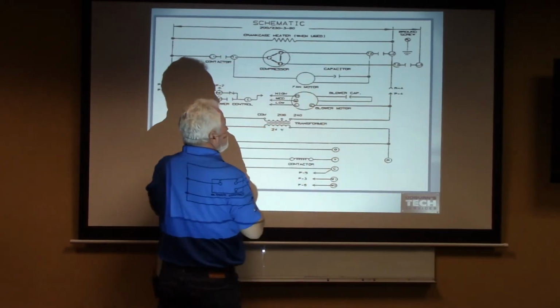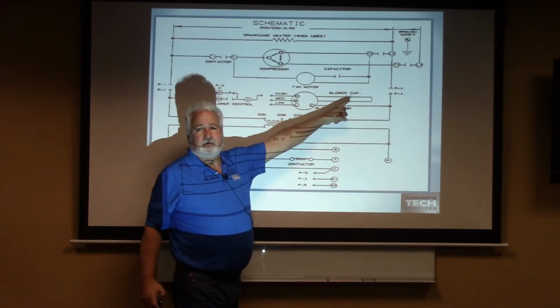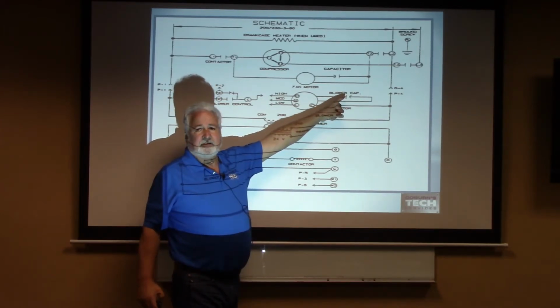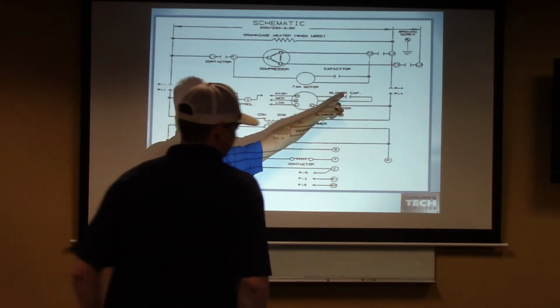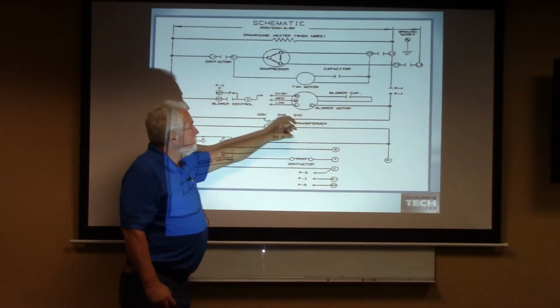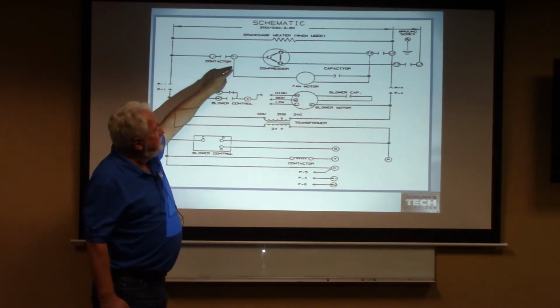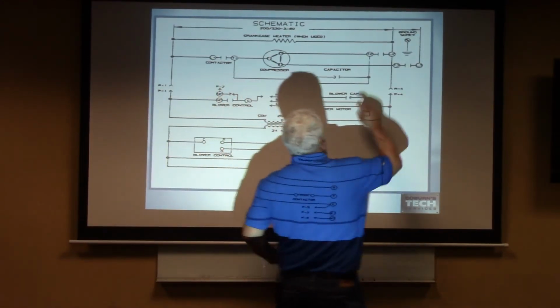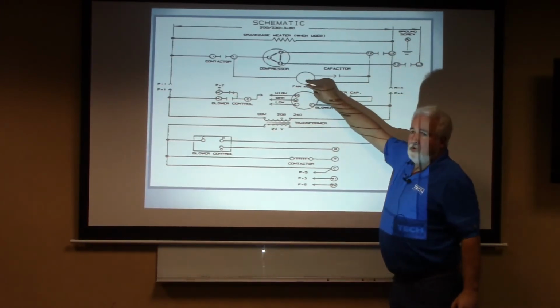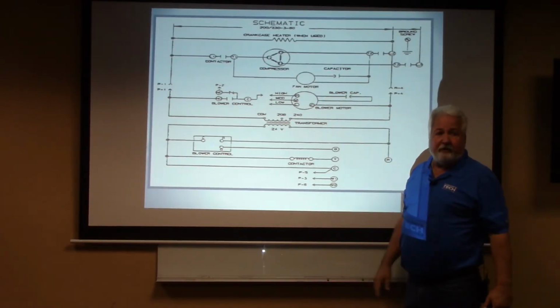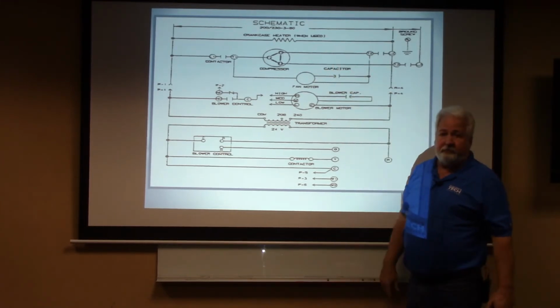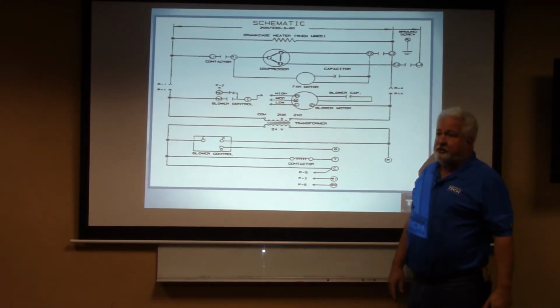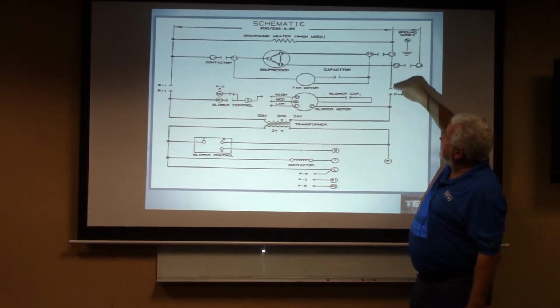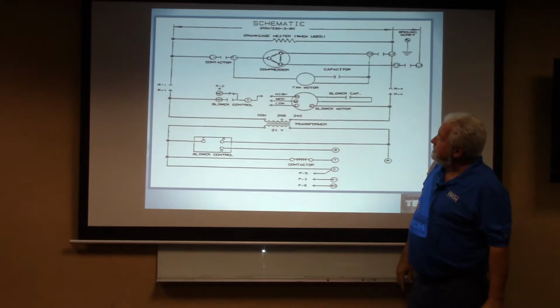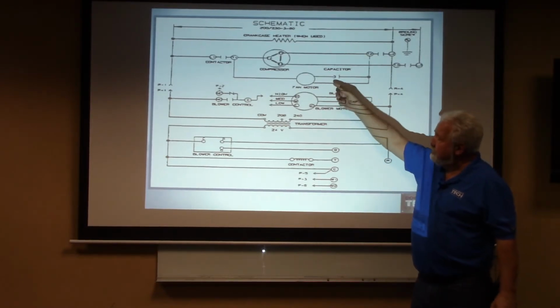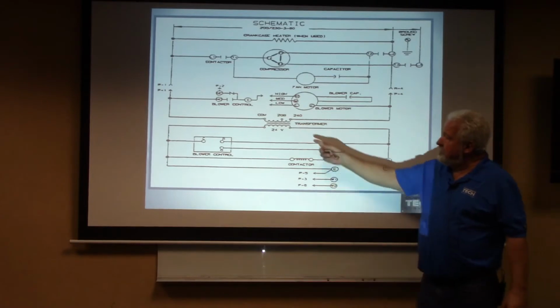Notice on here that that blower has a capacitor. If it has a capacitor, it's telling me right off the bat that I have single phase to that motor. I have line 1 going to my motor, and I have line 2 going to my motor. So I would have a single phase blower with a three-phase compressor. Is everybody seeing that? In this case, my condenser fan motor is the same thing, okay? Or my blower motor and my condenser fan motor are the same. Good?